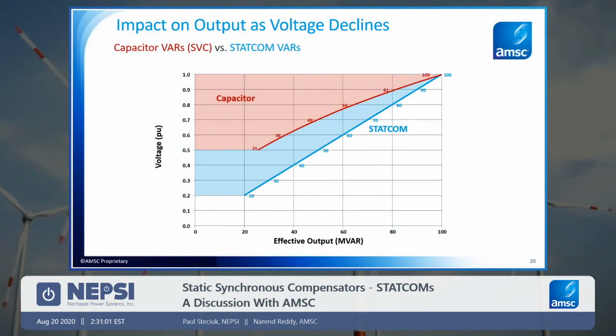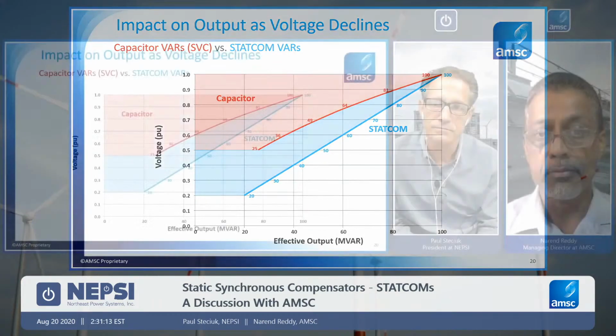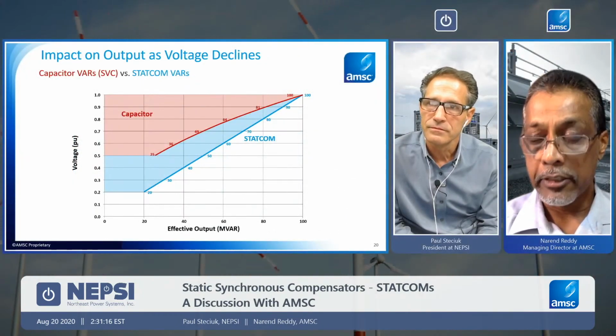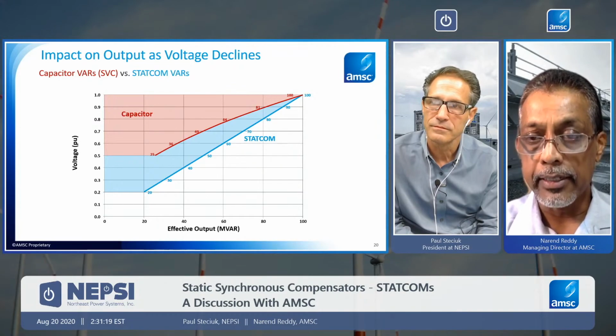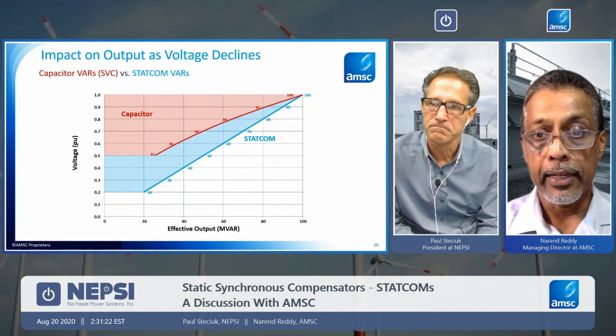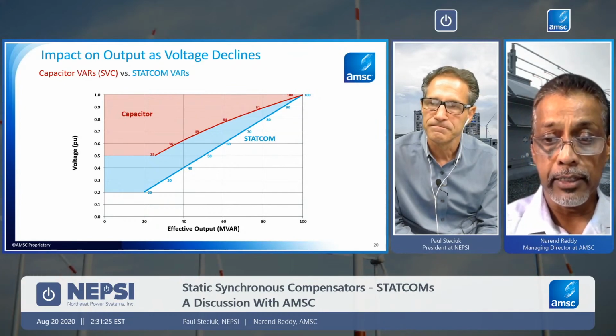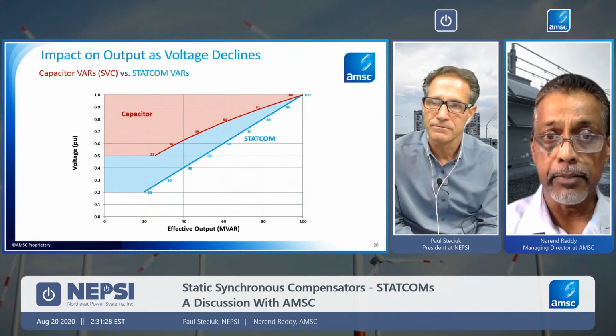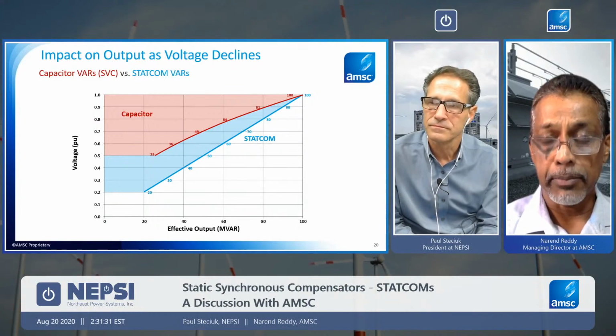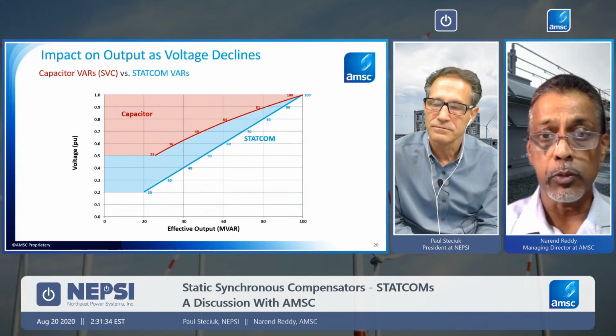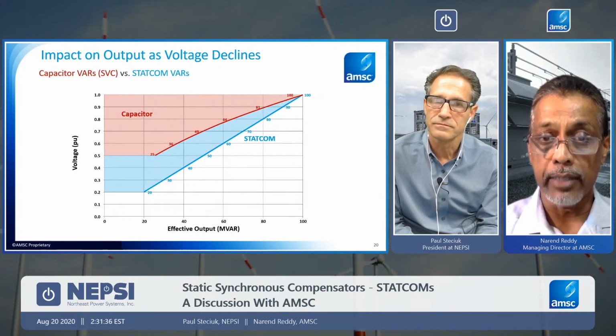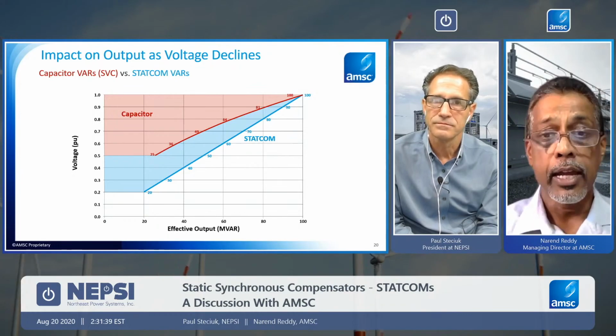So compare that with a STATCOM output on an equivalent scale, a 100 megavar STATCOM. You will see that, as I mentioned, it's linear with voltage. It's directly proportional to voltage. And so at voltages below nominal, you incrementally get more vars from the same rated device. That's one of the reasons we believe this technology is really picking up, and customers' applications are really dictating it, and standards are coming out where STATCOMs are now being required. Grid codes specifically ask for STATCOMs.